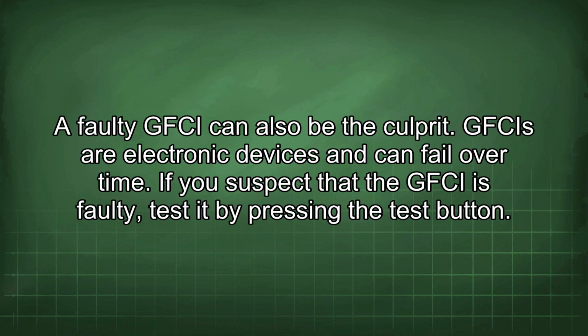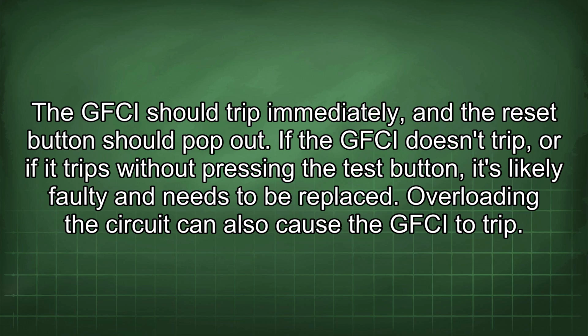A faulty GFCI can also be the culprit. GFCIs are electronic devices and can fail over time. If you suspect that the GFCI is faulty, test it by pressing the test button. The GFCI should trip immediately, and the reset button should pop out. If the GFCI doesn't trip, or if it trips without pressing the test button, it's likely faulty and needs to be replaced. Overloading the circuit can also cause the GFCI to trip.